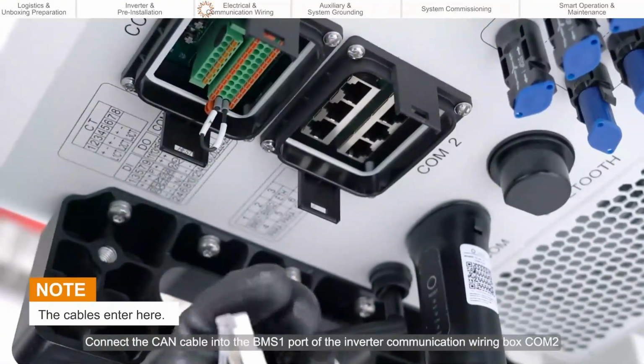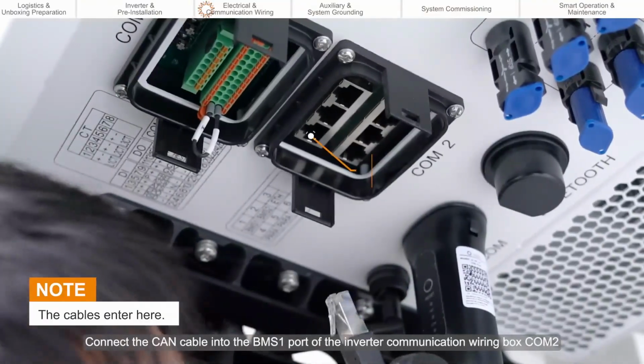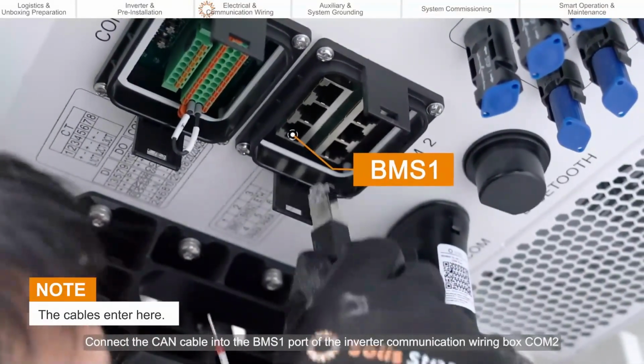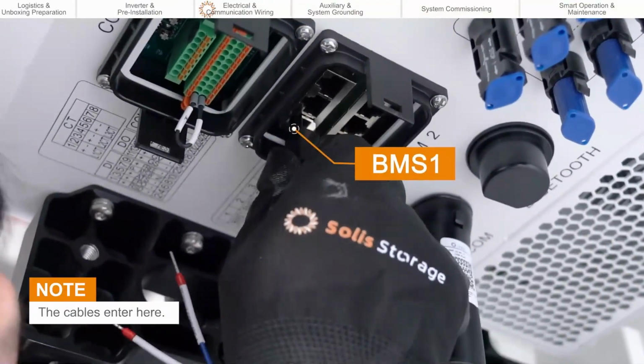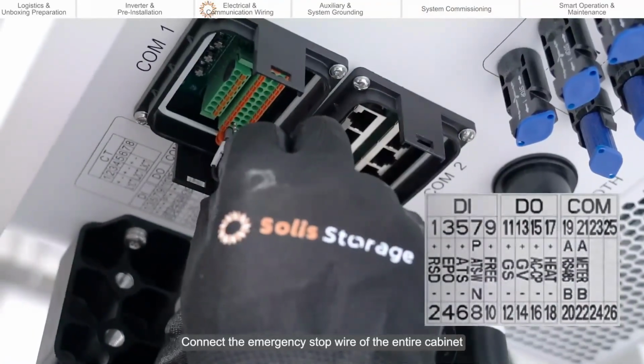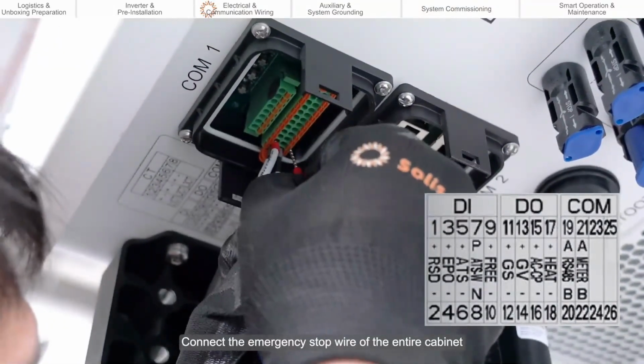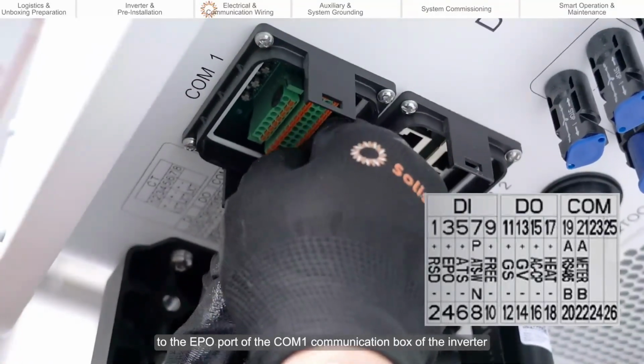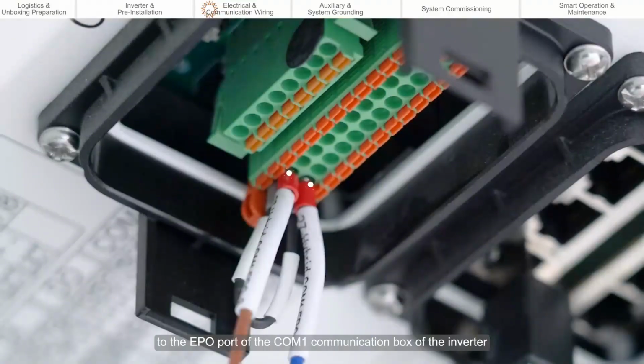Connect the CAN cable into the BMS1 port of the inverter communication wiring box COM2. Connect the emergency stop wire of the entire cabinet to the EPO port of the COM1 communication box of the inverter.